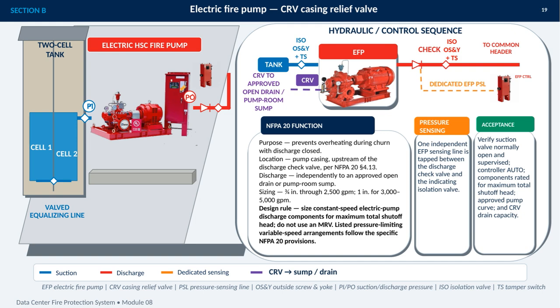The CRV is sized according to the pump's rated flow, 3/4 of an inch through 2,500 gallons per minute, and 1 inch for 3,000 to 5,000 gallons per minute. The dedicated pressure sensing line is tapped between the discharge check valve and the indicating isolation valve and connects to the electric pump controller. During acceptance, I would verify the suction valve is open and supervised. The controller is in automatic. All components can handle maximum total shutoff head. The pump curve is approved, and the CRV drain capacity is adequate.